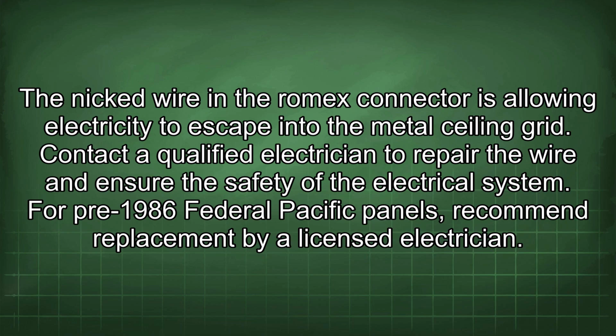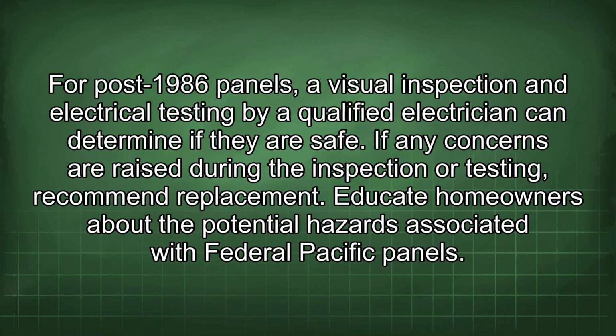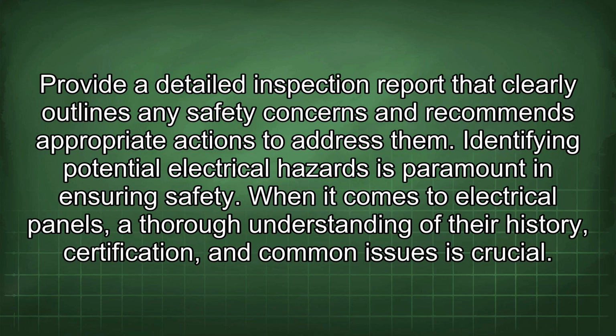For pre-1986 Federal Pacific panels, recommend replacement by a licensed electrician. For post-1986 panels, a visual inspection and electrical testing by a qualified electrician can determine if they are safe. If any concerns are raised during the inspection or testing, recommend replacement. Educate homeowners about the potential hazards associated with Federal Pacific panels. Provide a detailed inspection report that clearly outlines any safety concerns and recommends appropriate actions to address them.